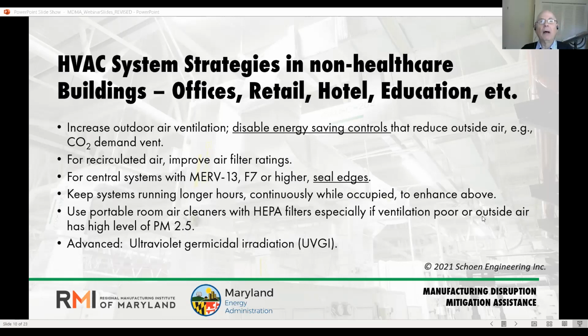Improve those filtration ratings—everybody in property operations has been hearing this over and over. But the underlying point, seal the edges, isn't getting enough attention. Once you put in a higher-rated filter, just like sealing a mask to your face, an industrial hygienist does the same for the filter inside the air handler. If you allow bypass around a filter that now has a higher pressure drop, you're simply reducing its effectiveness. So you must seal the edges—there are spring steel methods, gasketing methods, and even tight-fitting surfaces can do it.